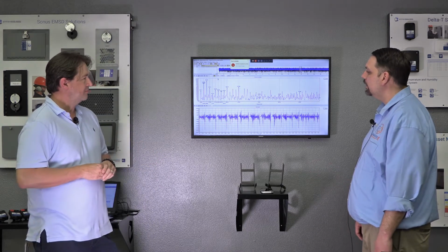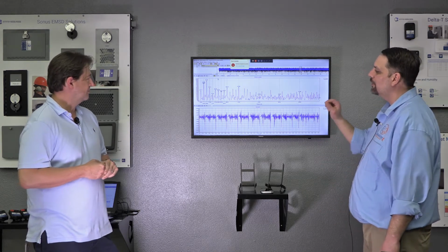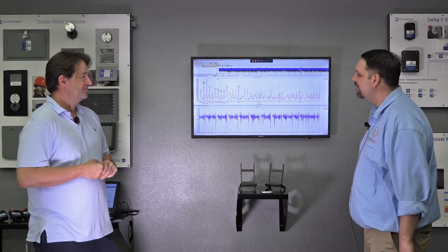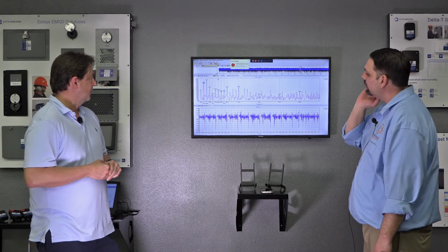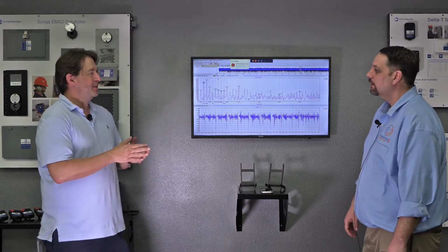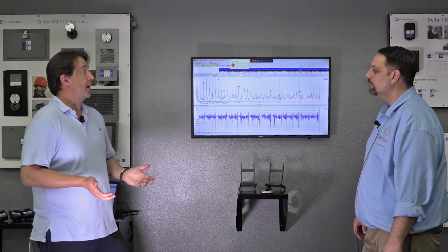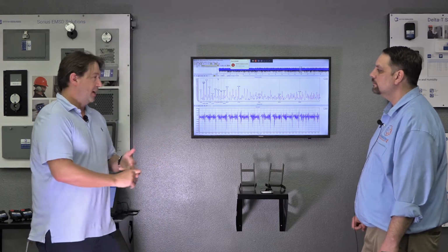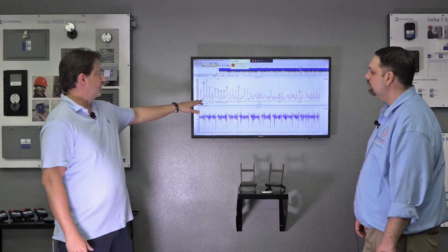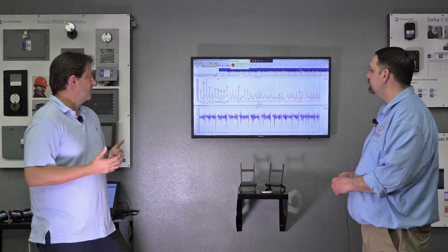Yeah, that helps tremendously, especially when you're trying to figure it out on your own, putting single points and going, oh, I think it's close, I don't know, when you could have one or two other issues going on. But this is very helpful. Especially, like you just mentioned, if we have one or two issues going on in the case of a bearing. How often has it been, well, is it my inner race? Is it my outer race? Is it my ball pass? Is it my cage? Now if you take a bearing fault calculator and input your values of RPM, and if it's a VFD, what's the line frequency, and how many balls are in there, you can calculate right down to the exact frequency that you'd look to see for the difference between an outer race versus an inner race. So it makes it very user-friendly.